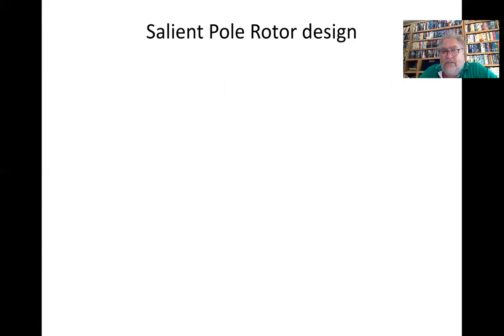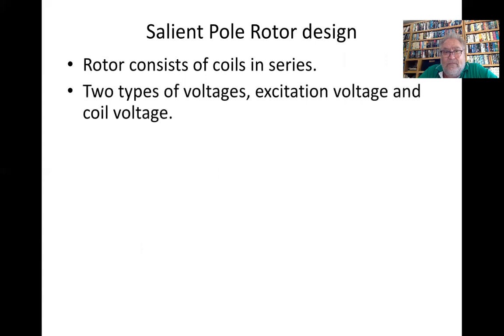Now if you look at salient pole rotor design, the rotor consists of coils in series, two types of voltages: the excitation voltage and the coil voltage. So R_coil = ρ l_mt times the number of turns per coil over the area of the conductor.